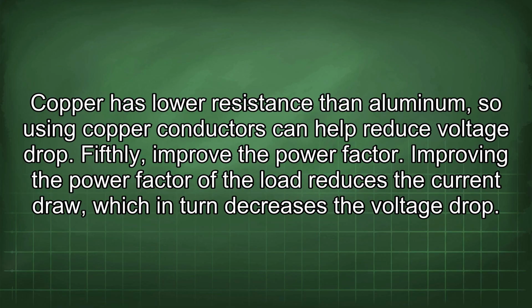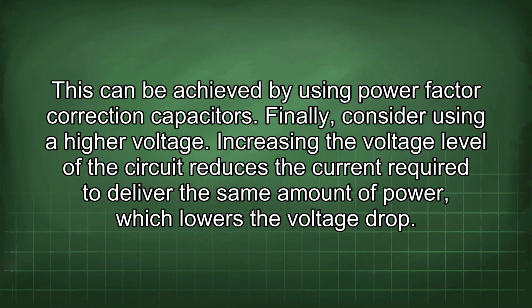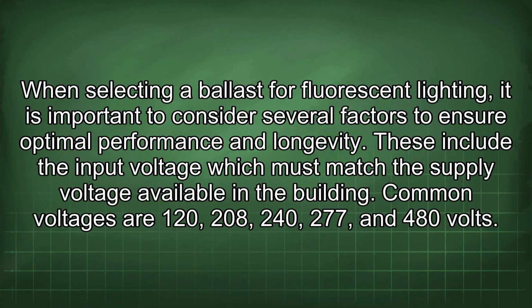Fifthly, improve the power factor. Improving the power factor of the load reduces the current draw, which in turn decreases the voltage drop. This can be achieved by using power factor correction capacitors. Finally, consider using a higher voltage. Increasing the voltage level of the circuit reduces the current required to deliver the same amount of power, which lowers the voltage drop. When selecting a ballast for fluorescent lighting, it is important to consider several factors to ensure optimal performance and longevity. These include the input voltage, which must match the supply voltage available in the building.